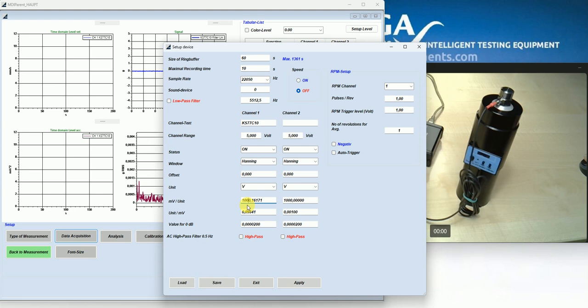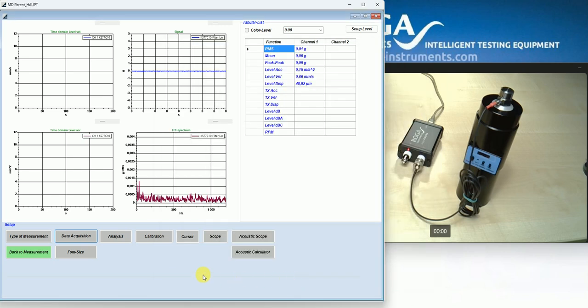Usually if you have the accelerometer, you can use the calibration sheet from the manufacturer and just key in here the related sensitivities which are mentioned on the manufacturer's data or calibration sheet. Another possibility is to determine the sensor sensitivity using a calibrator. This is what we will do right now.